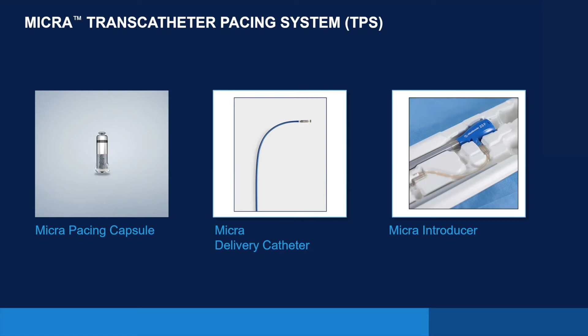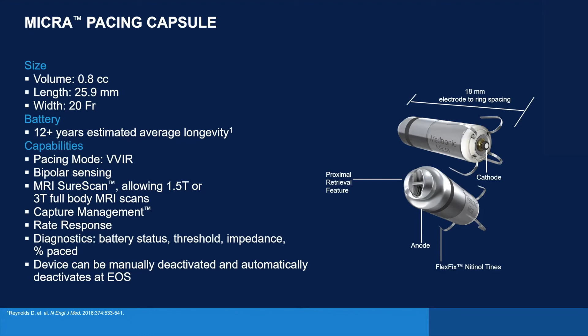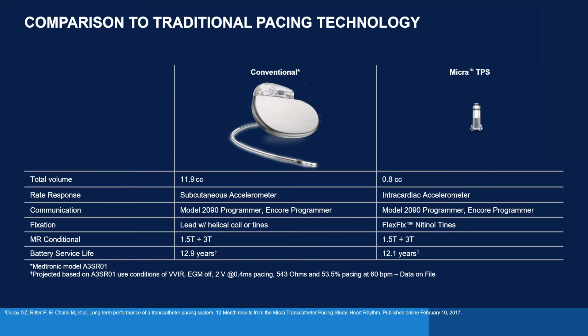Now, one of the interesting things is, although the device is basically a miniaturized pacemaker, because it's in direct contact with the heart muscle and doesn't need to transfer energy through a lead, the battery longevity is significantly enhanced. So much so that although it's a significantly smaller battery, it lasts as long as a traditional transvenous pacemaker. It has all the functionality. It has rate response. It's MRI compatible. It has multiple accelerometers, etc. So you can see, again, this is a more realistic comparison of the size difference. But you can see it has all the functionality and the longevity of a current transvenous pacing system.